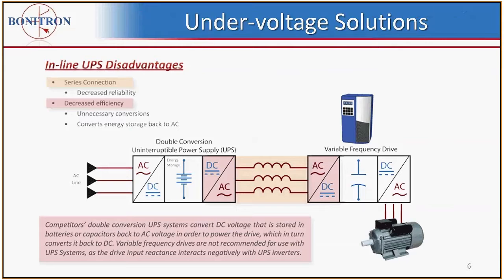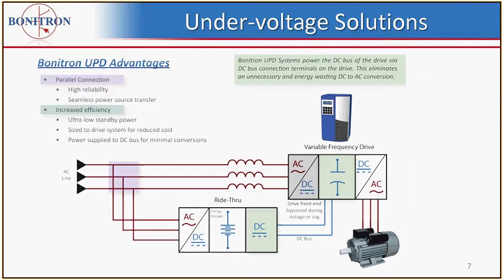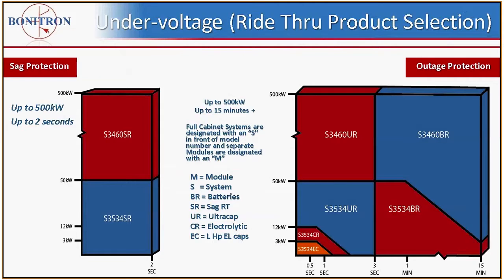Just a little review from our last presentation about connectivity. There are many ride-through solutions out there, and a lot of the solutions on the market right now connect to the front end of the drive, as opposed to the Bonitron UPD products, which are parallel to the drive, and this has many advantages that we covered in the first presentation. And there's only one conversion, AC to DC, and the voltage regulator booster will output DC to the DC bus of the drive. Once again, DC bus connections are critical for using UPD products.